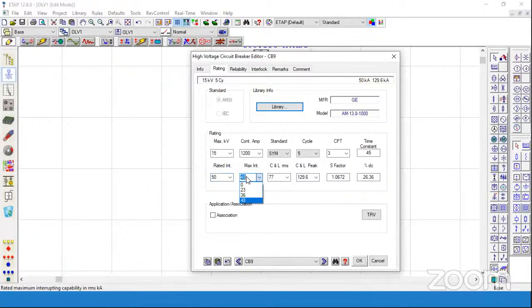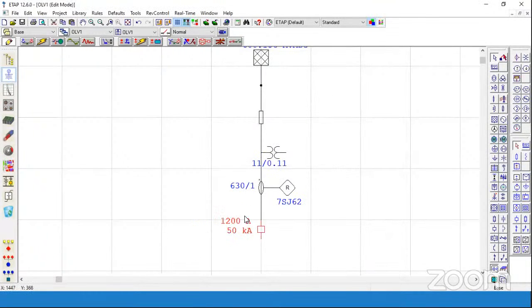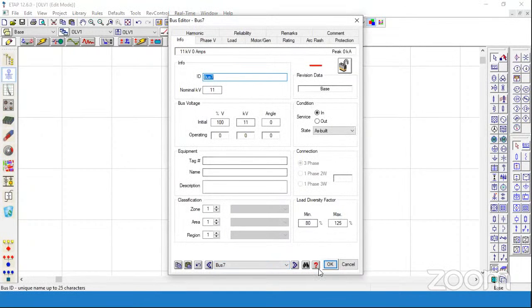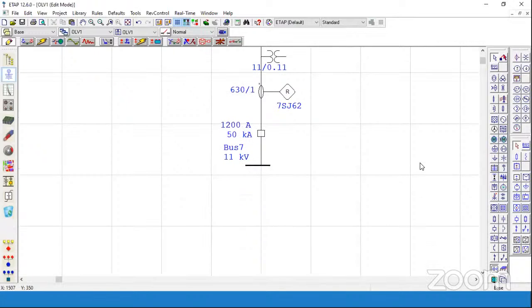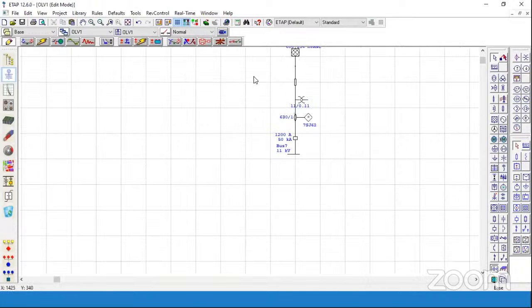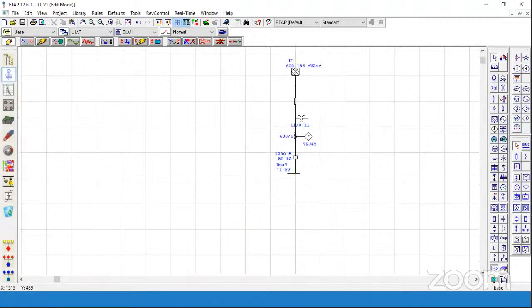Maximum make capacity, as I have increased the breaking capacity, will also change with a margin of 2.5. We can say symmetrical current. The time constant of the circuit breaker will automatically be fetched from this library. This much detail we need to give. Then we will have a bus of our premises, an 11 kV bus, automatically modeled. Then the transformer. Simply like this we have to model the entire single line diagram, not taking much more time.